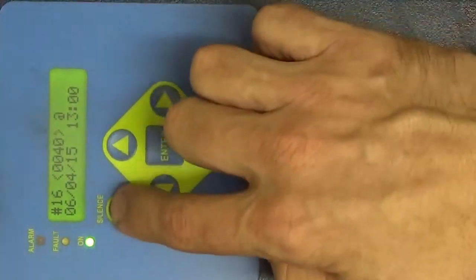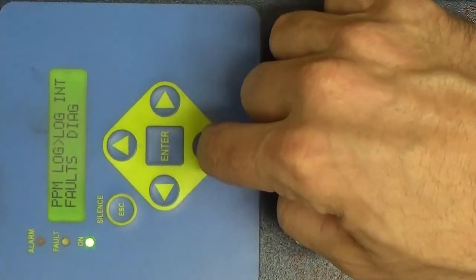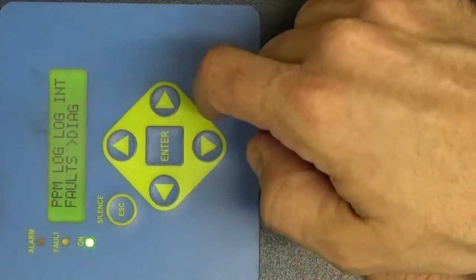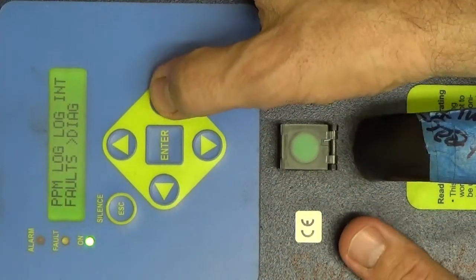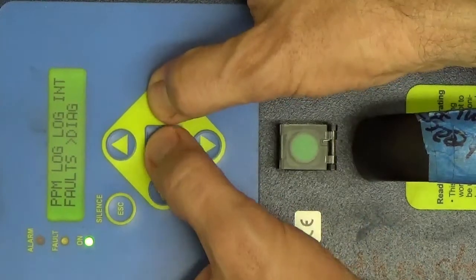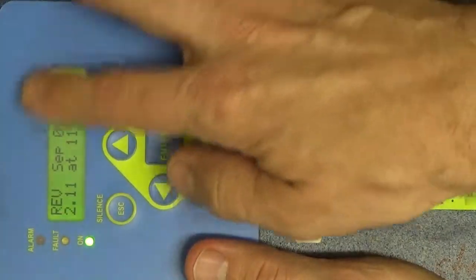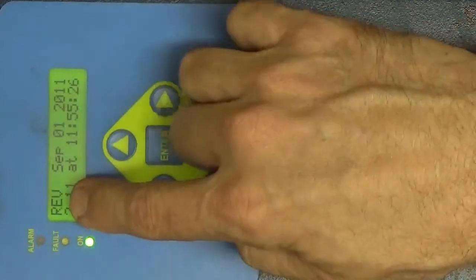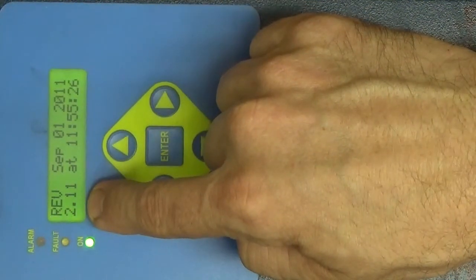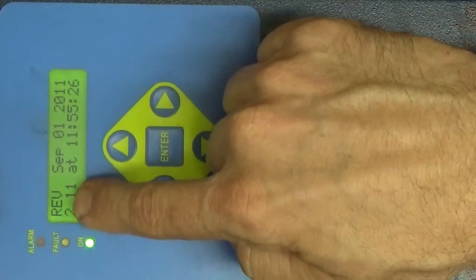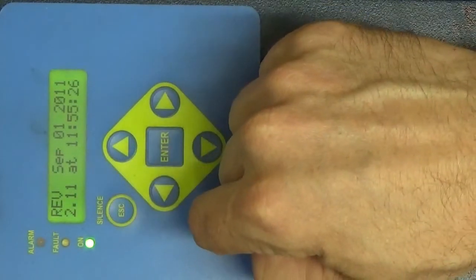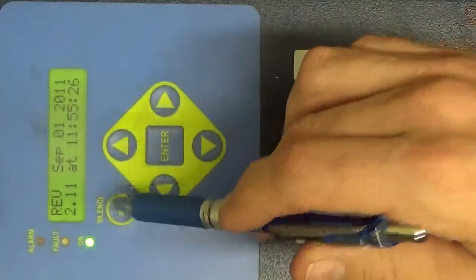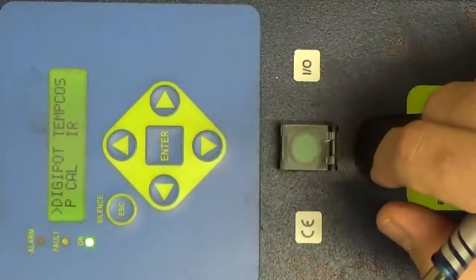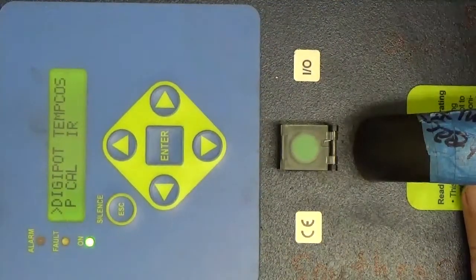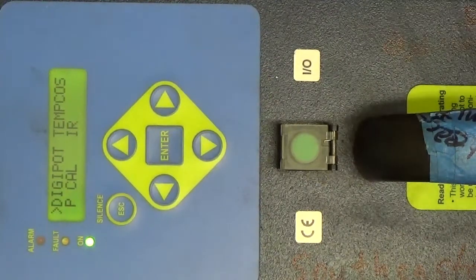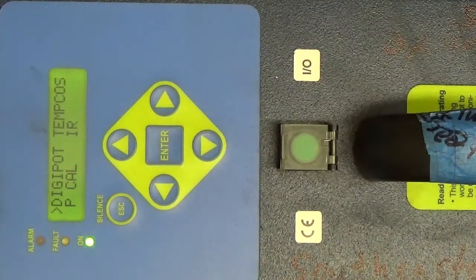Hit escape to get back to our main menu, and next thing we want to go to is the diag menu, D-I-A-G, and if you hold down the right arrow key and then press enter, you'll get to the diag screen. First thing you're going to see is the revision level of the software. This particular one says revision 2.11, which is fine. Next thing we're going to do is hit the escape key, and this gets to a second level menu where we can control some of the internal calibration settings of the unit.